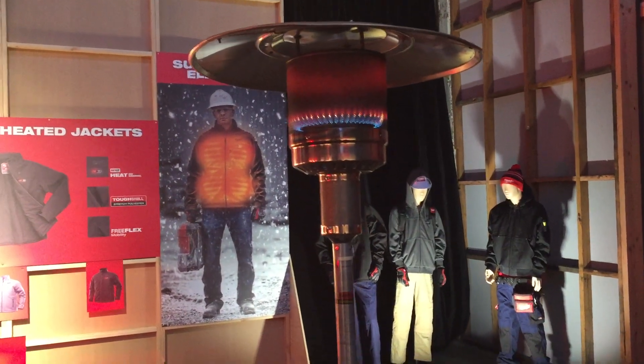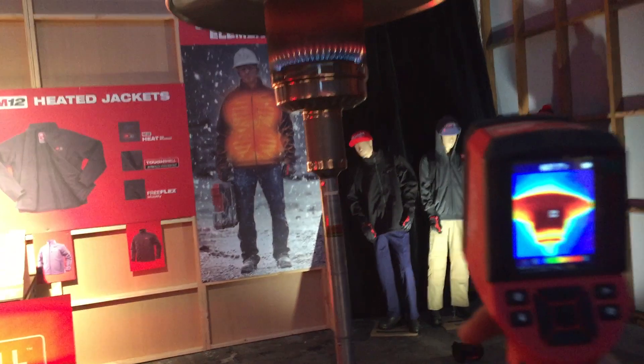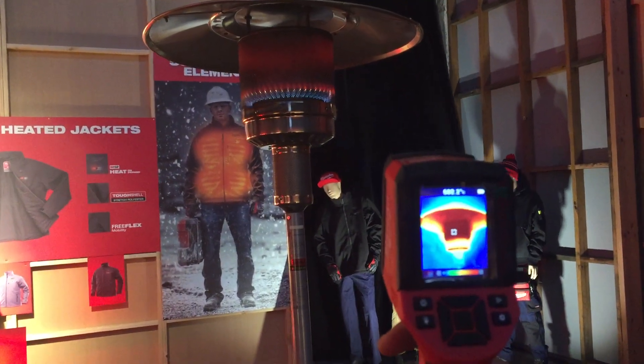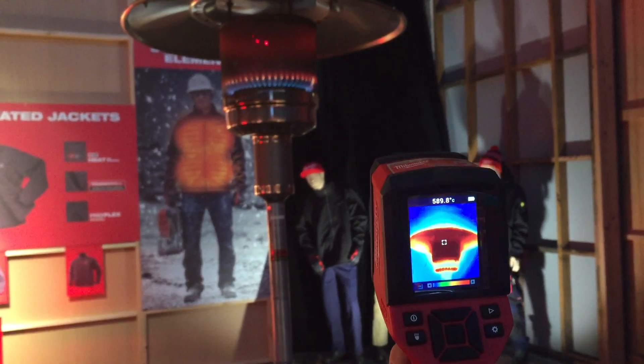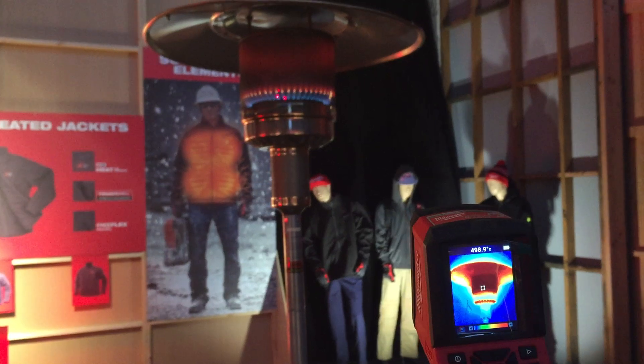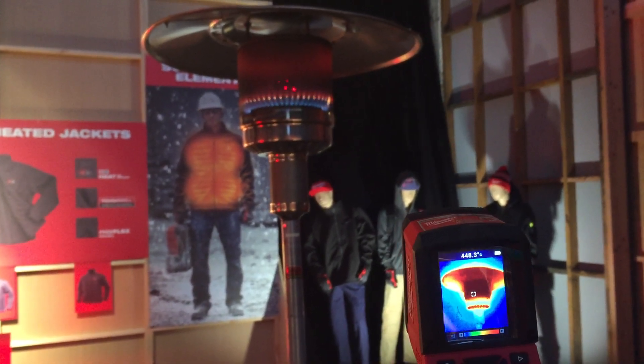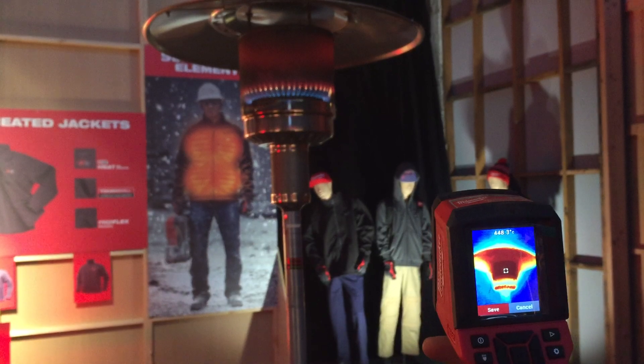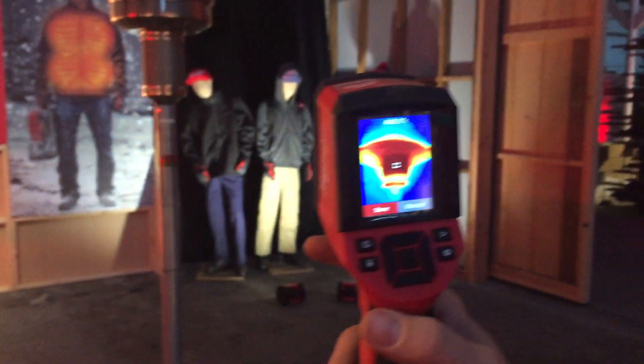For a working example, we've got a gas bayonet burner and you can see it's putting out quite an amount of heat in this room. In front of the camera we're reading around 620, 590, so we can get a good picture of where we're at. You can pull the trigger which shows a laser point, so we can get a more refined answer. Come down here under the flames, let it go, click once and it gives you a picture — at that specific point it's 448.3 degrees.